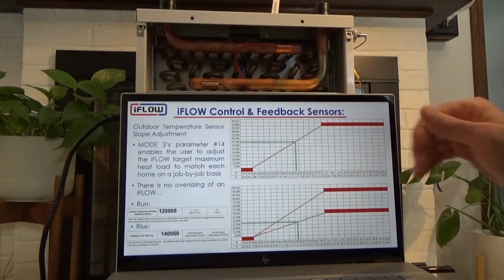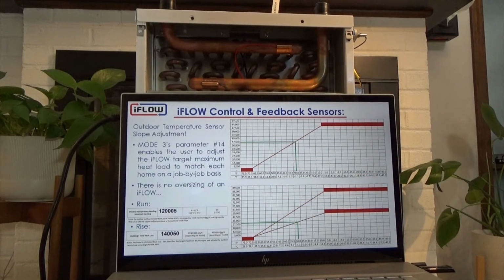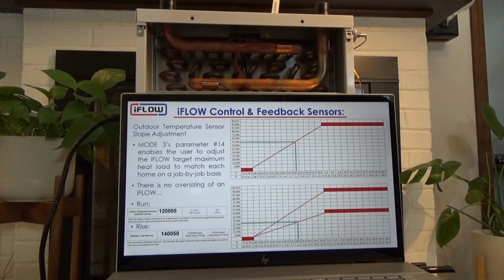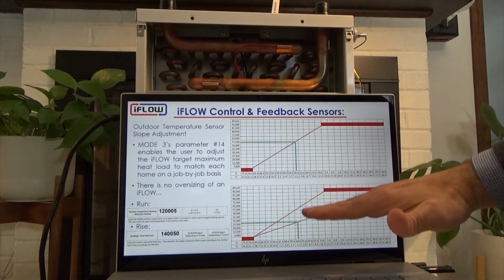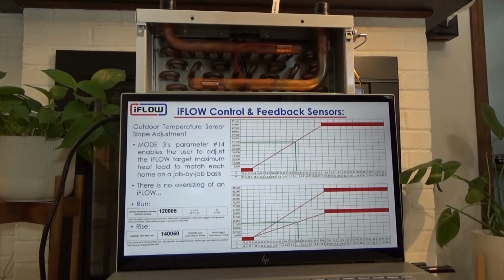So this is the value of the outdoor temperature sensor and why you should basically install it with each job and adjust it properly for each job so you can tailor the performance to each job specifically. So really there is no oversizing. We can put any unit in and then adjust the slope of the curve to determine the BTUs that we're delivering.